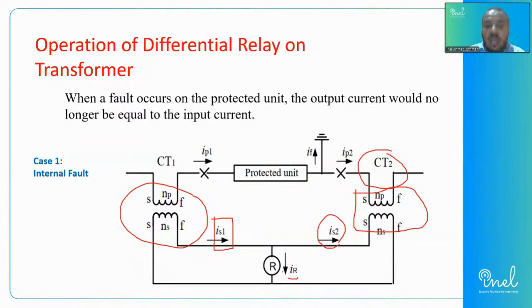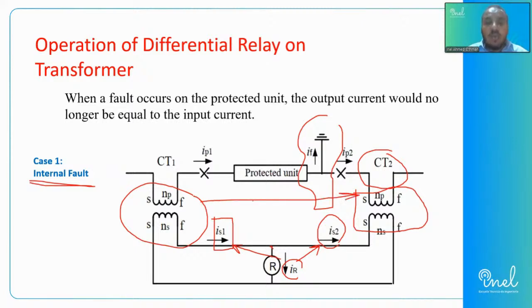And based on those IR, which is differentiating between IS1 and IS2 at a certain node, if there is a balance, normal, IR will equal 0, and at such a moment everything is good. If there is an internal fault on the protection zone, or protected zone, at the end, the zone between CT1 and CT2 is a protected zone. If there is an internal fault in between, there is no balance between IS1 and IS2, there is a value for IR, so the relay will start to act because the difference current, or differential current, is existing. That is case number 1.